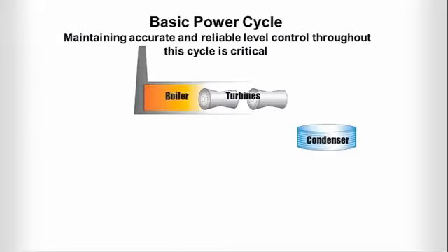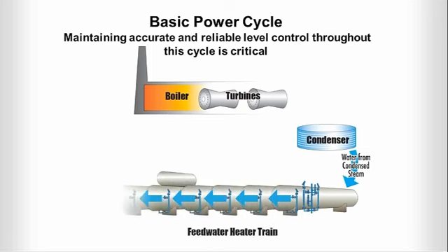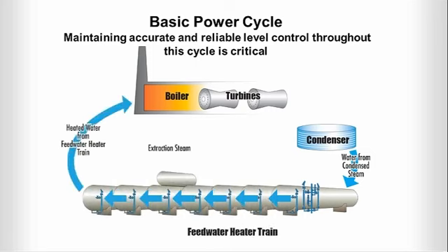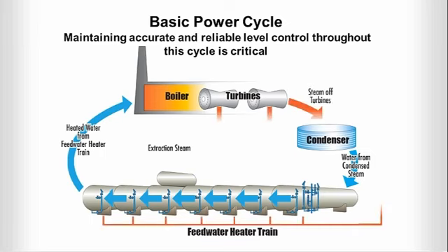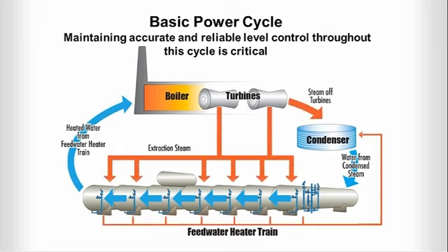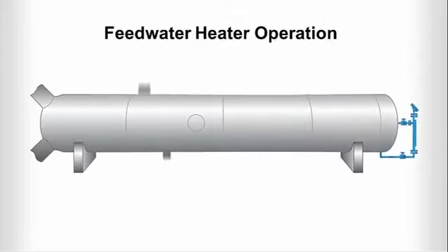The condenser is the beginning of the feed water heater's process, where condensed steam from the feed water heater drains and HP, IP, and LP turbines is routed through successive feed water heaters. At the same time, extraction steam from your turbines reaches the appropriate feed water heaters and the transfer of energy takes place. Maintaining accurate and reliable level control throughout this cycle is critical to achieving the final feed water heater temperature that your process requires. Let's take a closer look at how this works.